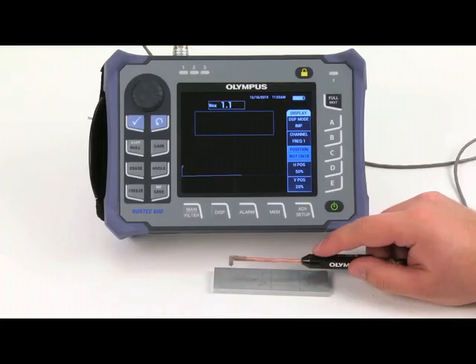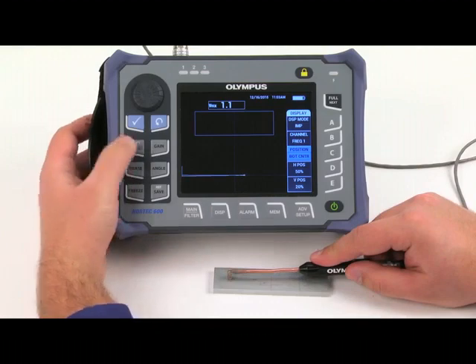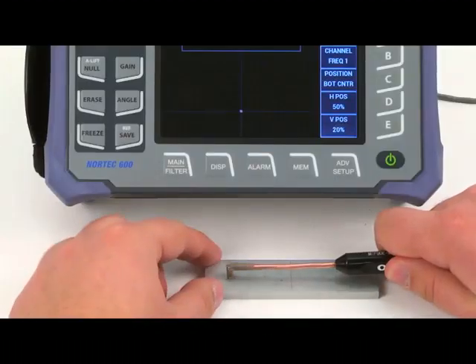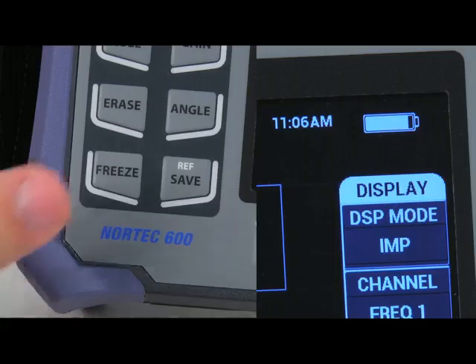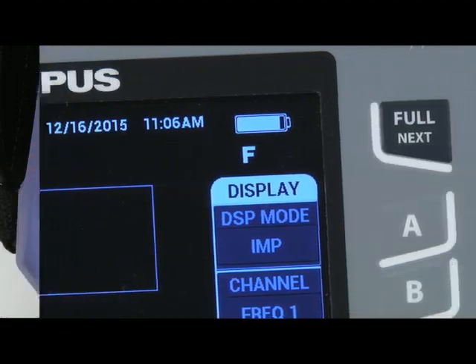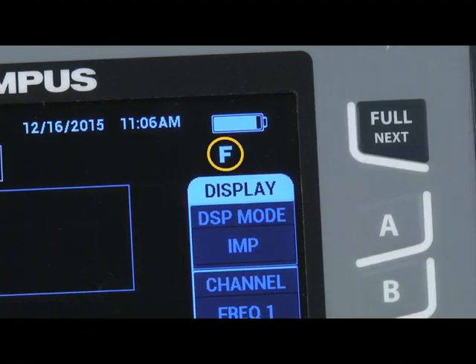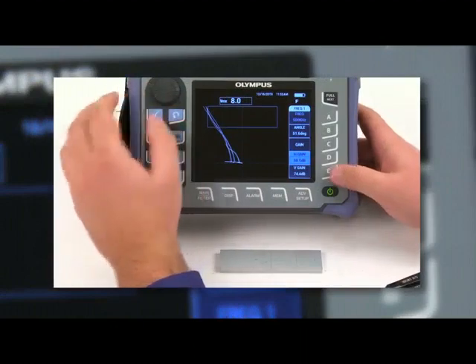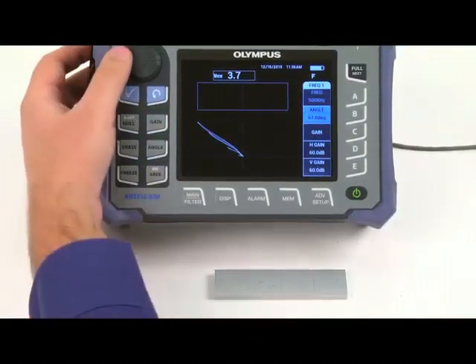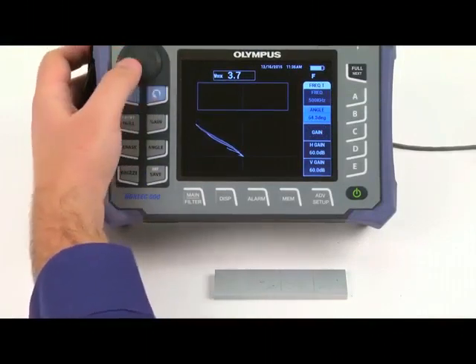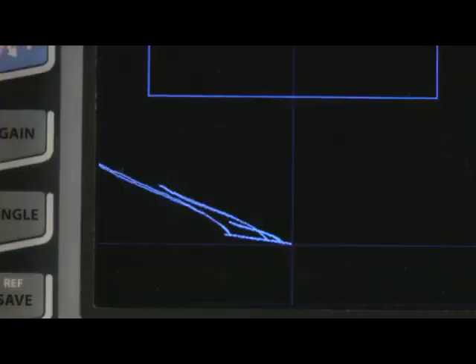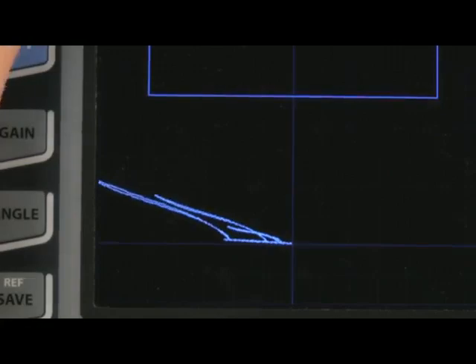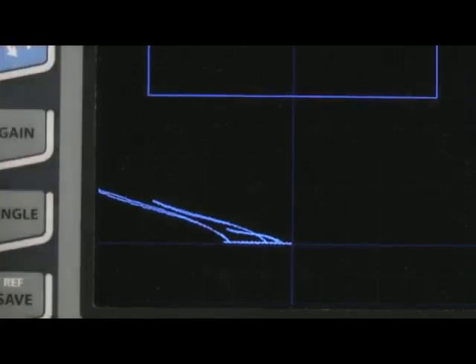Now put the probe on a defect-free area and press null once. Scan the sample and press the freeze key. Once in freeze mode, an F should appear below the battery indicator. Freeze mode enables the user to calibrate the signal using both hands. Press the main key to fine-tune the horizontal angle and try to set it as flat as possible. Use the knob to adjust the angle and the checkmark key to go from coarse to fine-tuning.